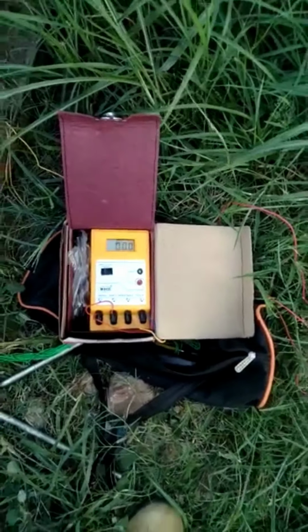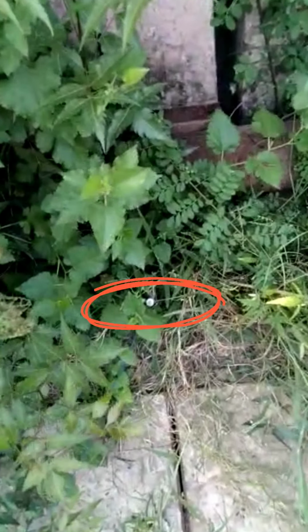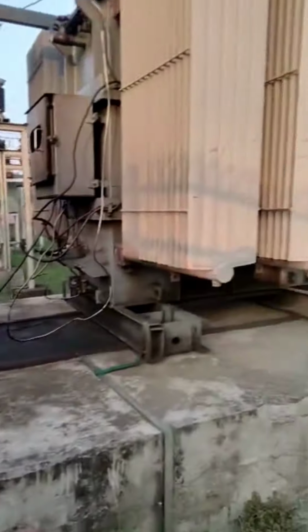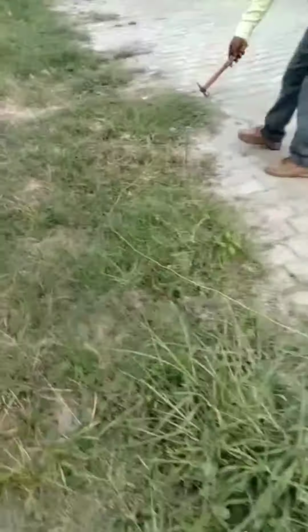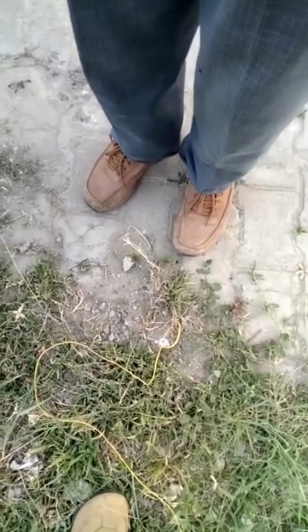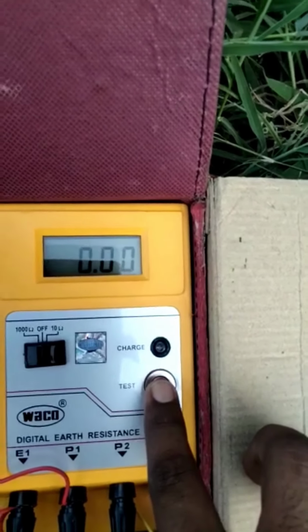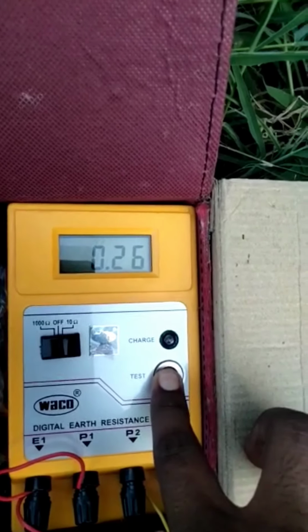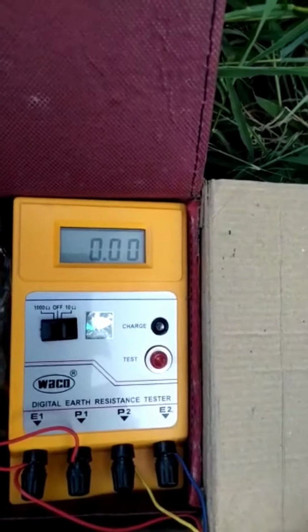Let us see how to measure the earthing resistance of a substation. Here one earth electrode is placed here, then another earth electrode is placed here, and the third point of the earth tester is connected to the earthing pipe, the earthing of this substation. Then we can check the earth value by pressing the red button. Here we get 0.26 ohm, very good.